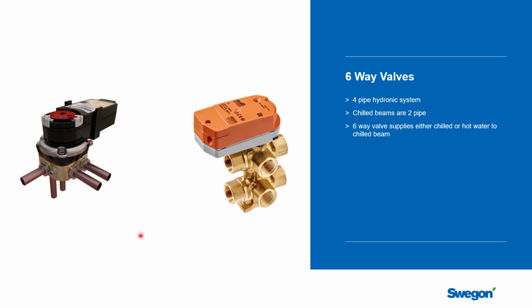Now, something else you're seeing a lot being used in chill beams these days are six-way valves. So if you're not familiar with them, let me introduce them to you. This is what they look like. This is a valve that Swegon offers. It's actually a small valve. It's sized to be actually mounted right on the chilled beam. Where we use this is on what we would call our bulkhead or our Paragon product. And that product is used in hospital patient rooms or hotel rooms or kind of single bedroom type applications, which means it's one chilled beam, one control zone. So you are going to have a valve that does that.